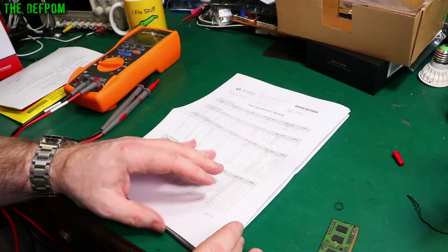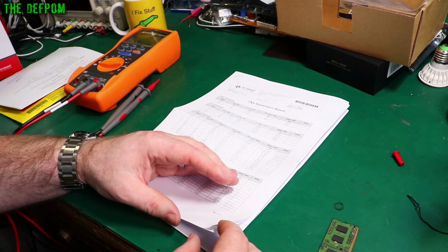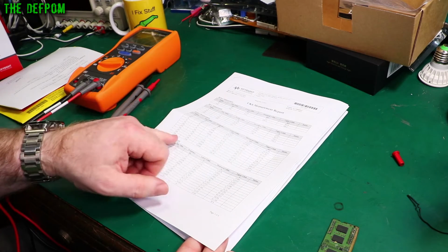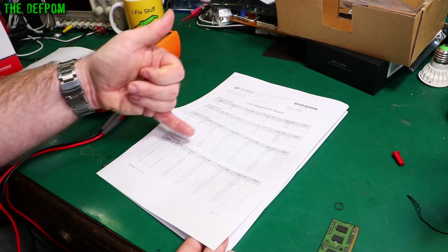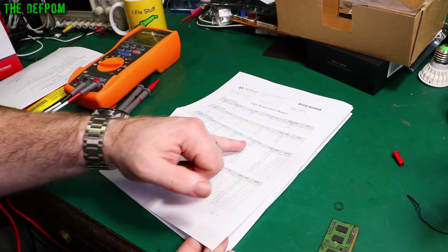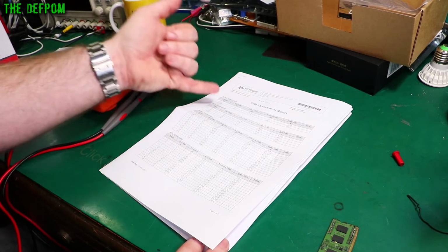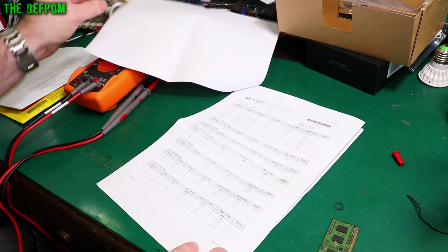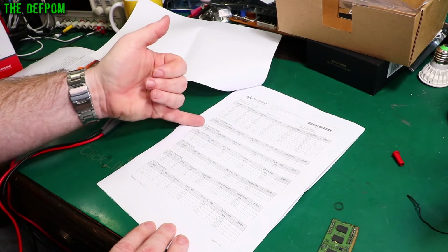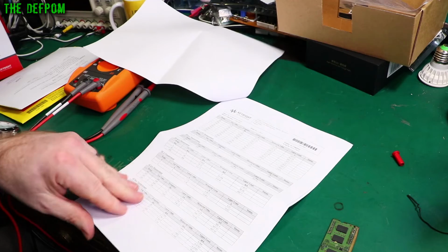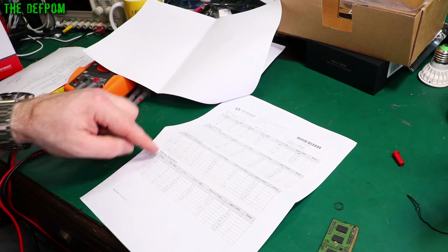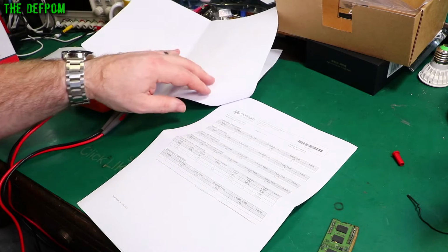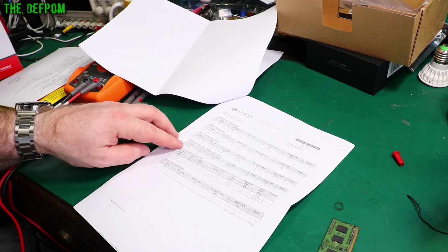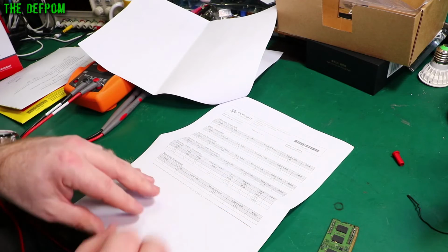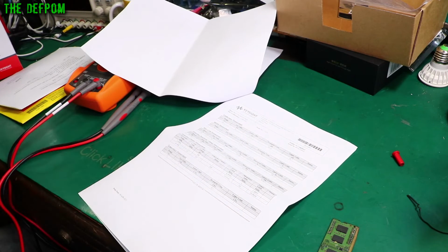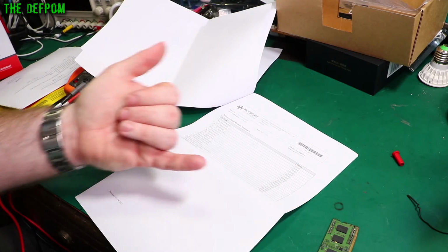They look nice enough. So here is the calibration document which I downloaded from Keysight and obviously printed out. It shows all the different measurements, so each range, the modes, the actual test frequencies, what the limits are, lower limit, upper limit, and what actually resulted. You've got DC millivolts, DC volts, AC millivolts, AC volts, AC volts again, AC volts low pass, DC microamps, DC milliamps, DC amps, AC microamps, AC milliamps, AC amps, capacitance, resistance, conductance, diode measurement, duty cycle, frequency sensitivity, voltage measurement. So that's interesting. That must be like a threshold for the sensitivity. Frequency counter, temperature, and that's the final summary of all the results being passed.